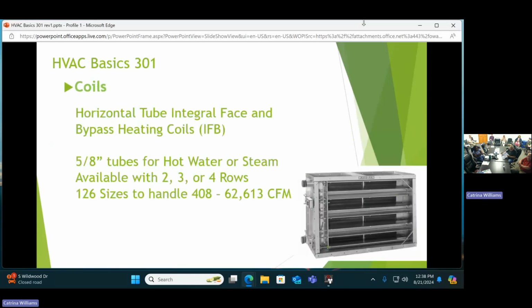So I'll summarize the coils for you. The IFB is horizontal. You see a picture of it there, the finned element going horizontally. 5/8" tubes for all of these coils we're talking about right now, available in 2, 3, or 4 rows for capability of how much heat you might need. Look at the variation you can offer, 126 sizes, and airflows from 408 to 62,600 CFM. These boxes here, the finned elements go from 36 inches long to 120 inches long. So it can handle a pretty good amount of air, as you can see.